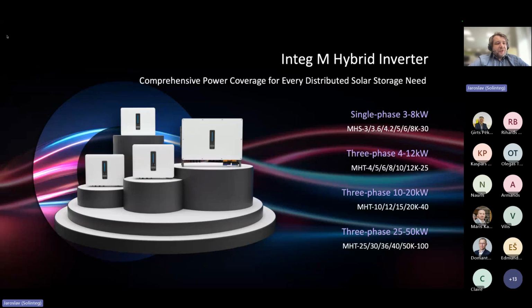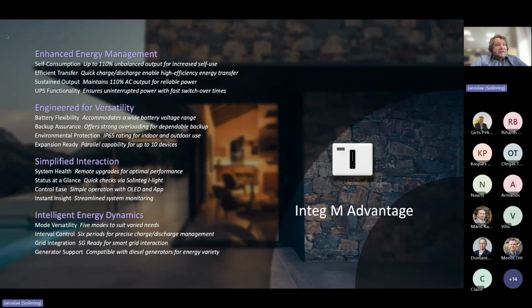And now we come to our C&I solution. These are the inverters in the range of 25 to 50 kilowatts with a charging and discharging current for the battery of 100 amps. This is our Integ M Advantage. That means enhanced energy management. You can better use your self-consumption of the energy because all the inverters have unbalanced output, and this helps to increase your self-consumption.